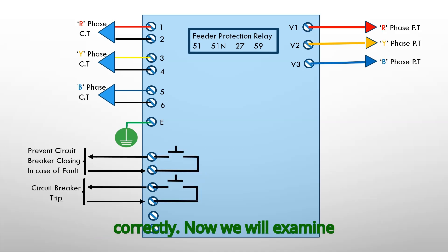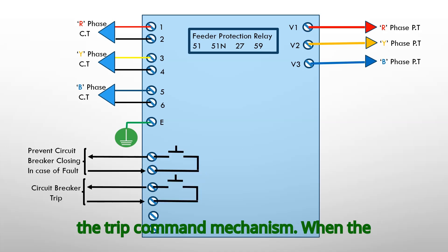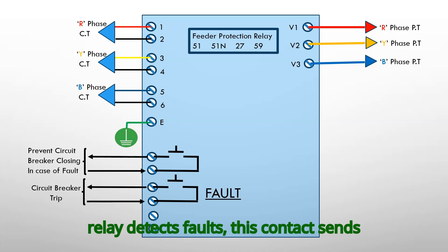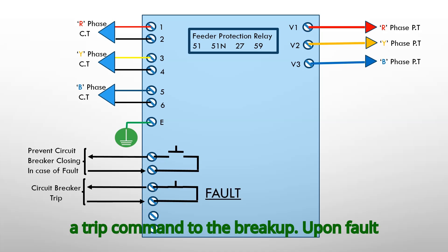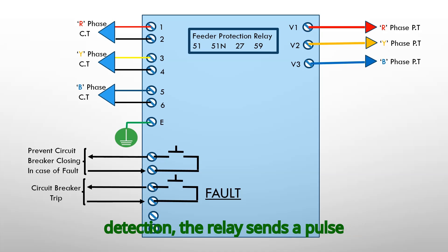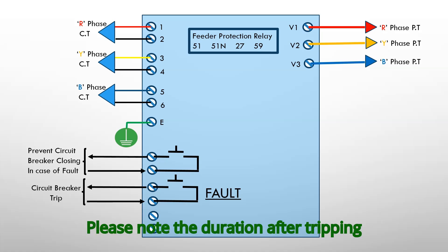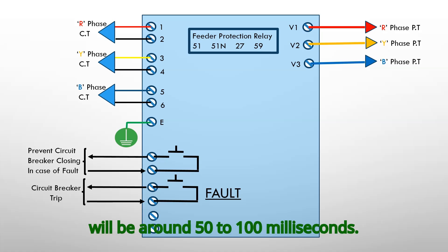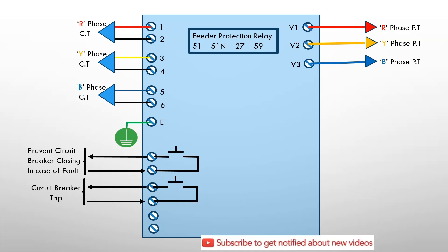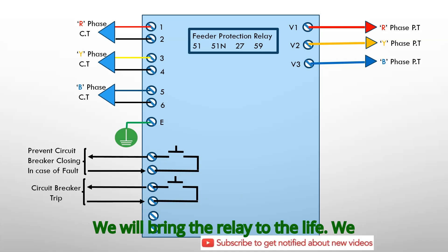Now we will examine the trip command mechanism. When the relay detects faults, this contact sends a trip command to the breaker. Upon fault detection, the relay sends a pulse command to the tripping coil and initiates immediate breaker tripping. Please note, the trip duration will be around 50 to 100 milliseconds.